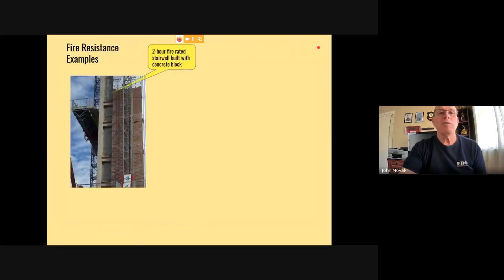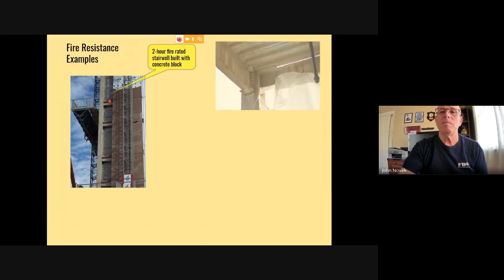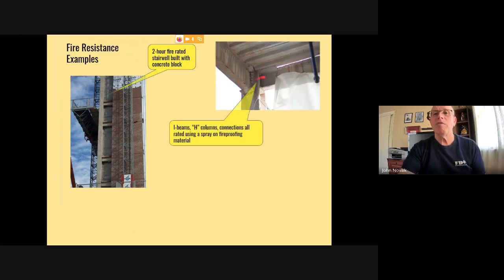Some examples of fire resistance. In this case over here, we have a part of a hospital under construction. This is a stairwell. You can see the stairwell is block, so you're getting a 2-hour fire resistance rating. The structural steel members, the H columns, and the I beams are all sprayed on fire protection. Up here, we can see the spray on fire protection on the underside of the floor decking and on the connections, the bolt connections, the I beams, and the H columns.